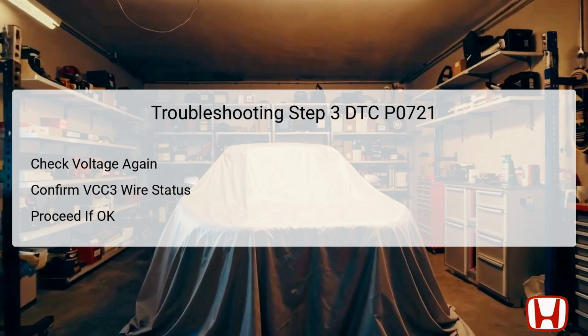A reading of about 5 volts here indicates that the VCC3 wiring is functioning correctly. If confirmed, you can advance to the next troubleshooting step. Conversely, if the voltage is inadequate, it signals an open circuit within the VCC3 wire that requires repair before continuing further diagnostics. This step is designed to provide clarity on the power supply line that feeds the Countershaft Speed Sensor, ensuring it receives the correct voltage for optimal performance.